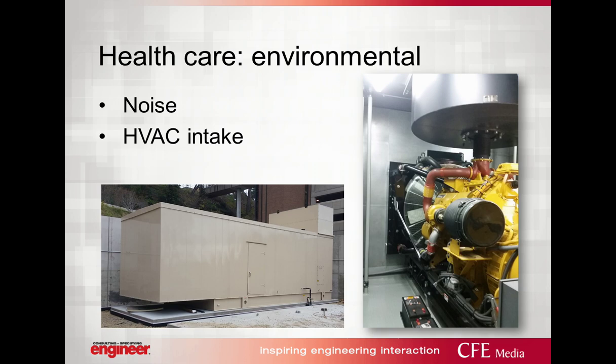Now, if your emergency source is a generator set, you will have environmental concerns that can be exacerbated with healthcare applications. Many of the guidelines for healthcare and patient care areas have noise limits associated with them. FGI, LEED, WELL certification, ASHRAE, etc., all have recommended or required noise criteria. Additionally, you may have state or municipal noise sources and property line requirements. Here in Illinois, for example, Title 35 of the Illinois Administrative Code is highly restrictive, and standby power systems are not exempt.